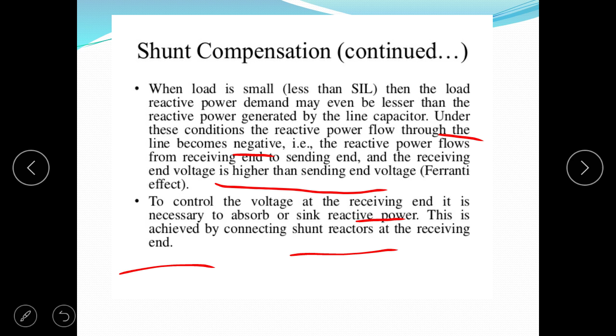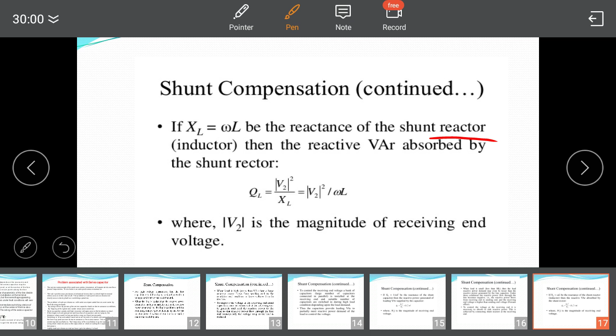Now to control the voltage at the receiving end, it is necessary to absorb or sink reactive power, which is done by connecting a shunt reactor at the receiving end. It means the Ferranti effect is reduced by connecting a shunt reactor at the end of the line. A shunt reactor absorbs reactive power from the line, which compensates the reactive power in the line, due to which voltage at the receiving end becomes stable. So if XL equals omega L is the reactance of the shunt reactor, then the reactive power absorbed by the shunt reactor is V2 square upon XL, that is V2 square upon omega L, where V2 is the magnitude of the receiving end voltage.